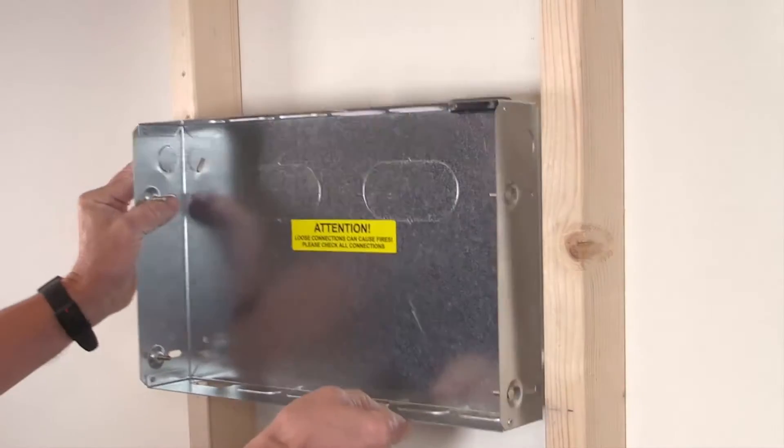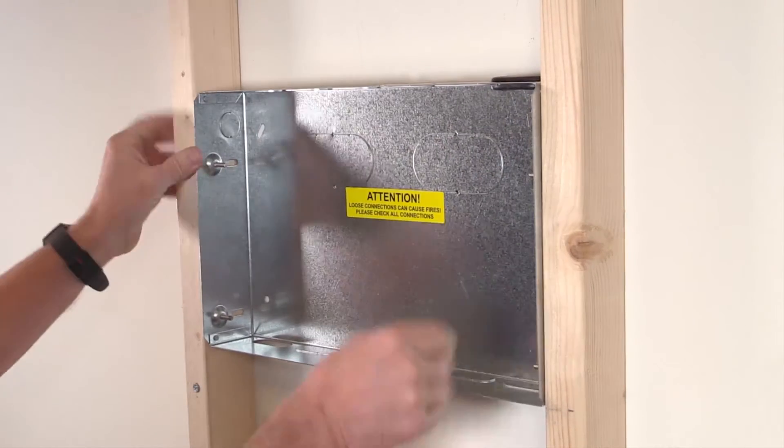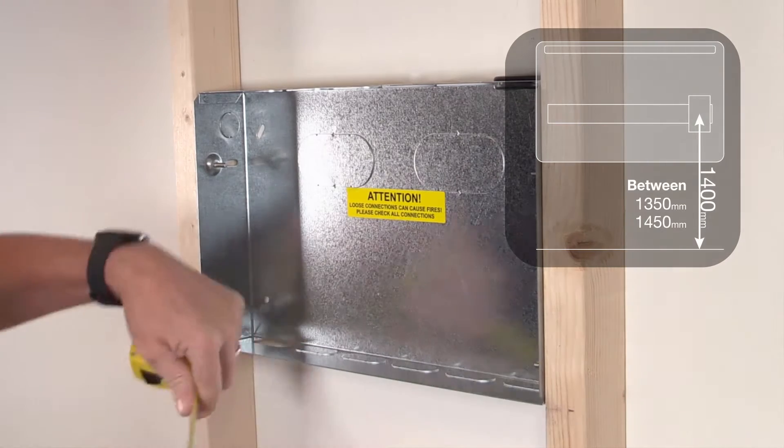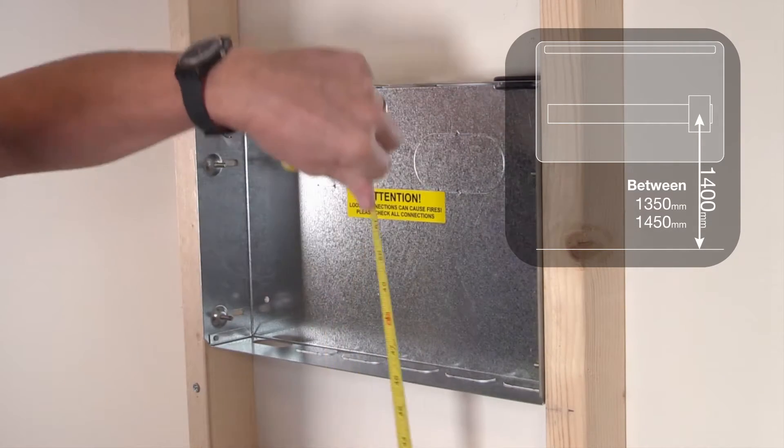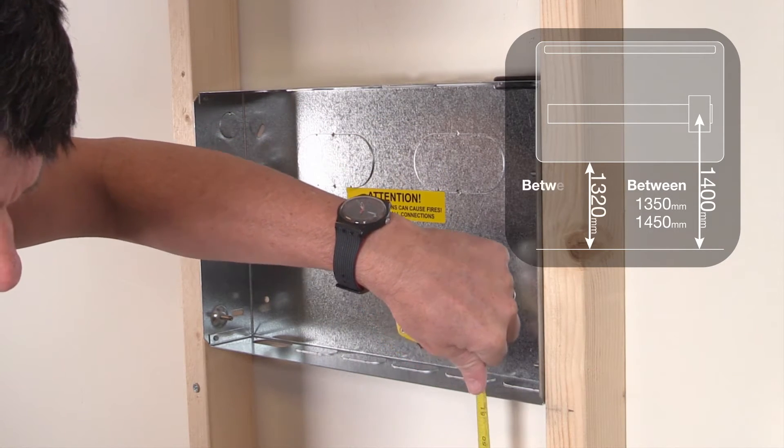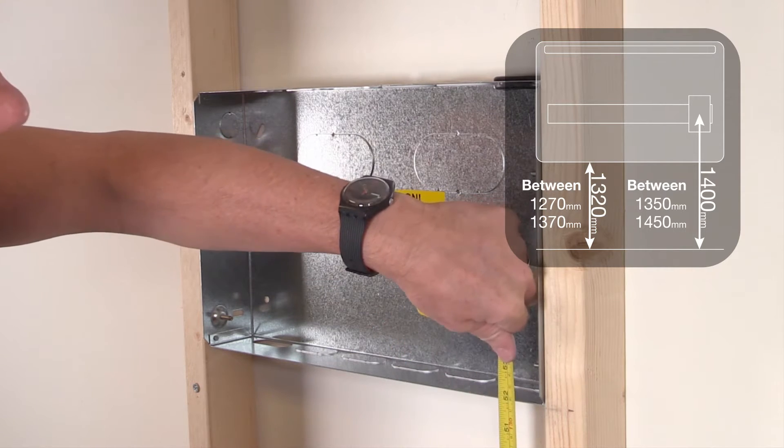To comply with Part M of the building regulations, which states that the main switch should be 1400 millimeters from the finished floor height plus or minus 50 millimeters, the bottom of the back box must be installed at 1320 millimeters from the floor plus or minus 50 millimeters.